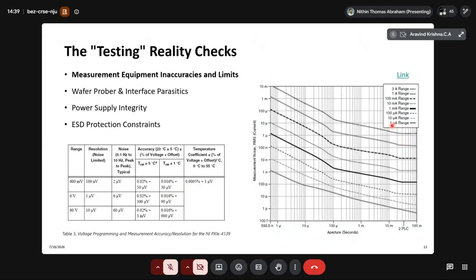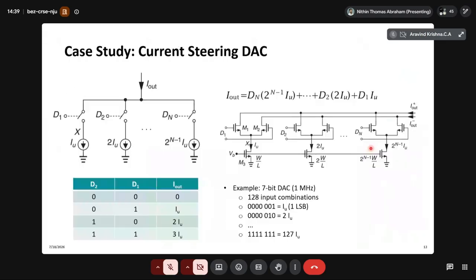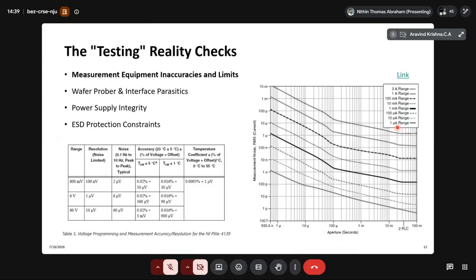But we cannot measure the next bit. We need a higher current setting to measure more than 1 microampere current. We have current up to 127 microampere. So we have to force the equipment to a higher range. But if you see, there is no 127 microampere range. So we have to set the equipment in this 1 milliampere range. If we set it in the 100 microampere range, the equipment will saturate at 100 microampere. So even if you are measuring 127 microampere, you will only measure 100 micro. You cannot measure 127. So you always need to set the equipment in a higher range.